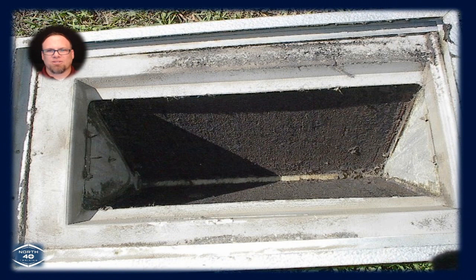Here's another fun picture. Now this is fun for us, but it wasn't fun at the time. This is just the opposite. Here we have the technical advisor going out on a job in which the furnace, a brand new furnace, kept tripping limit. Nothing that they could do would get this thing to quit tripping limit. Well, it was your standard installation in which the furnace was going to be replaced, but not the coil and not the air conditioning system at all.